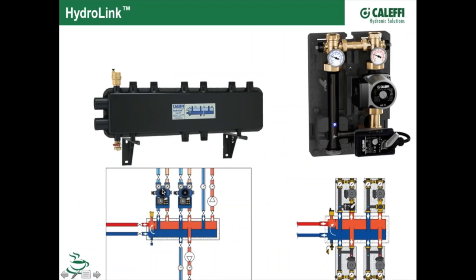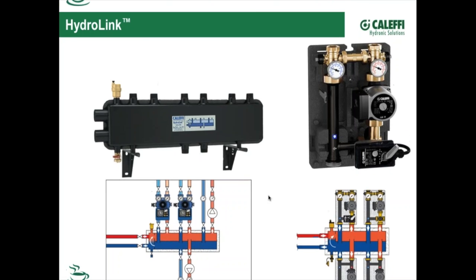Now you could have a fixed temperature going on that. You could have one with thermostatic. We offer it with a motorized mixing valve on it. So now you've got the ability, if you do have a system that requires different temperatures, high temperature, low temperature, mid temperatures, we can do that right on this distribution box. So no piping in the boiler room, just come from the boiler to the device, put your pumps on, and go right out to wherever your heat emitters are. So it's a really simple solution to not only make sure that you get the proper flow rate with the separation function here, but also that you've got the ability to mix and match different flow rates, different pumping stations, different flow requirements out at the distribution side. Whoops, sorry.